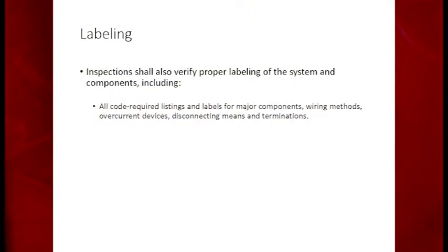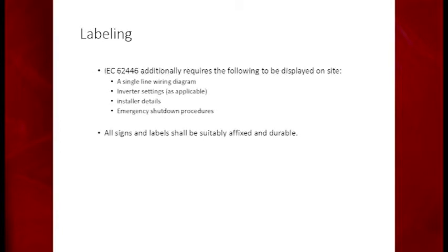Wiring methods, the wiring diagram must be in this system. Labeling is important, this is what everybody needs to see and understand. So the labels for the major components, wiring methods, disconnect means and termination. There has to be a single line wire diagram, inverter settings, what this inverter is supposed to be set on, installer details, emergency shutdown procedures. Very key.